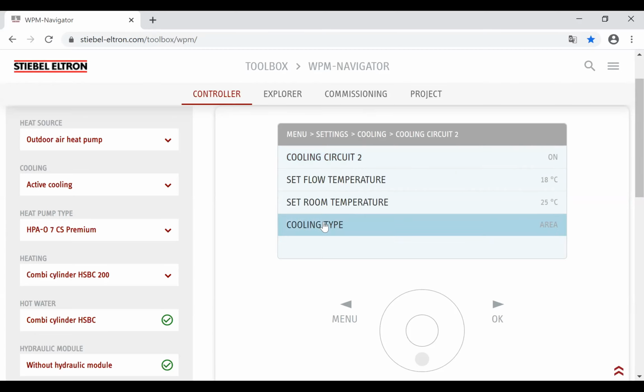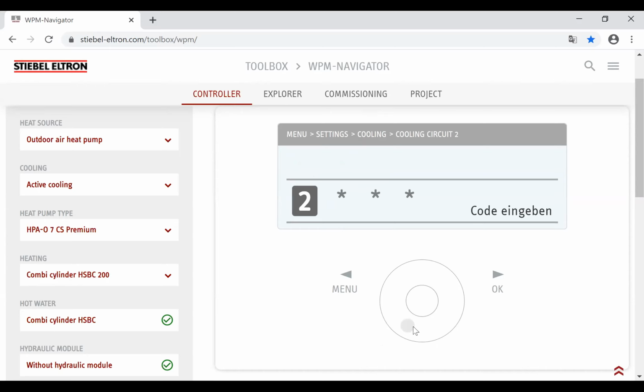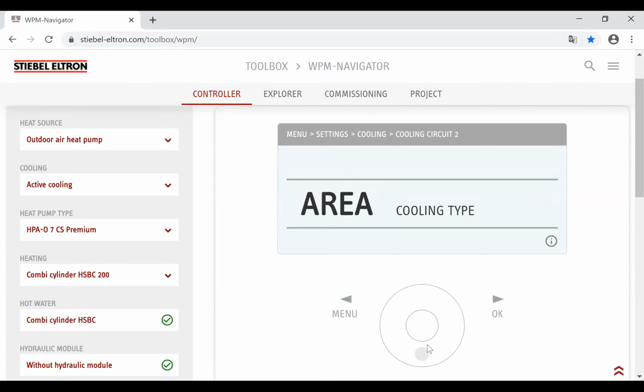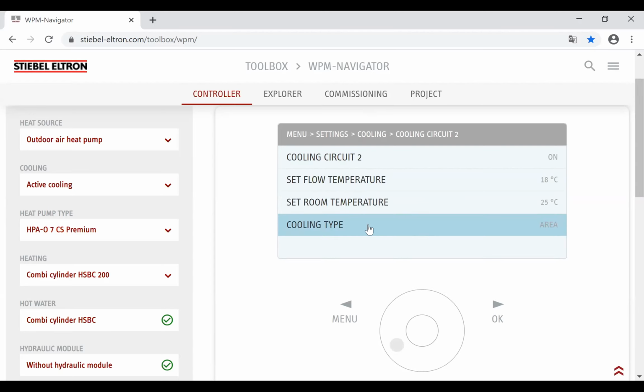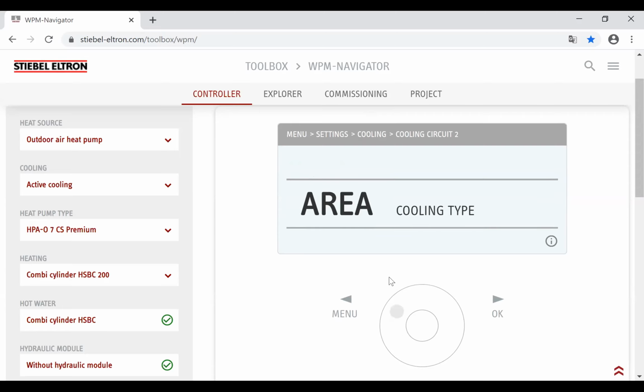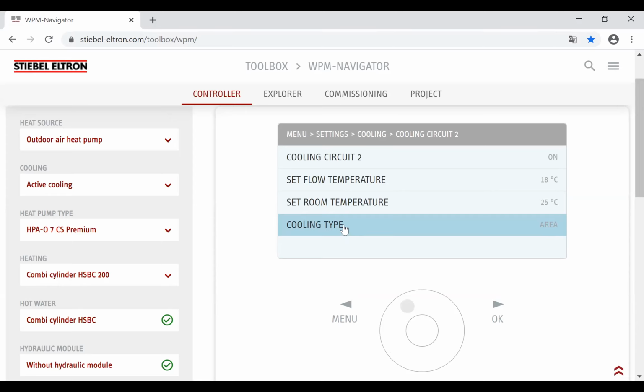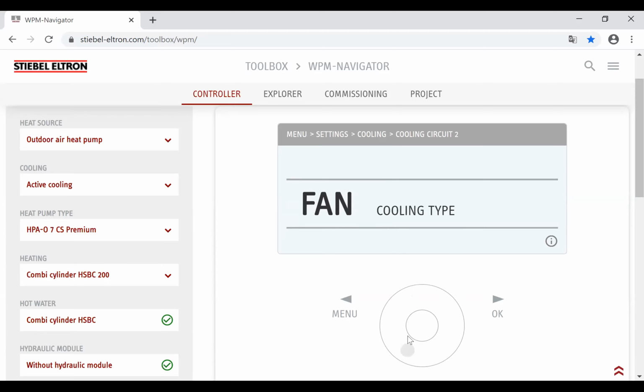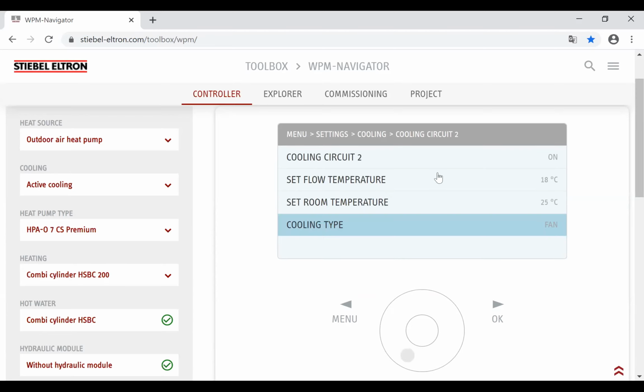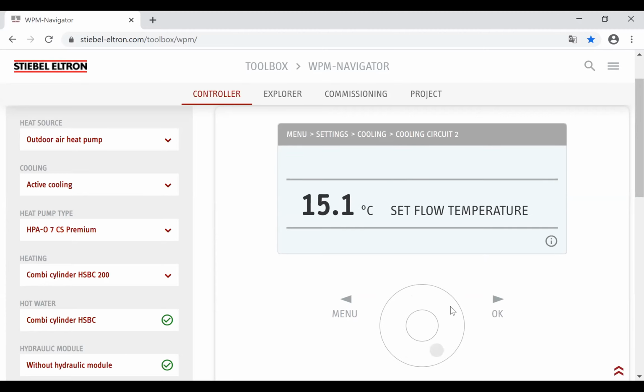Now, we have 2 types of cooling to choose from, okay? And that is area cooling. Let's just throw a code in here. You have area cooling. Does that give me the option to change it? Or we have fan coil. The difference between these two types of cooling is fan cooling is a fixed temperature cooling. So if I was to put that back on fan type cooling, set flow temperature, that's it. It's fixed temperature, and we can set that temperature down as low as we can possibly go, because that's the temperature we want to send to our fan coil units. Now, fan coil units, remember, have condensate drains. So they're picking up the condensation formed inside the unit and sending it out the drain.